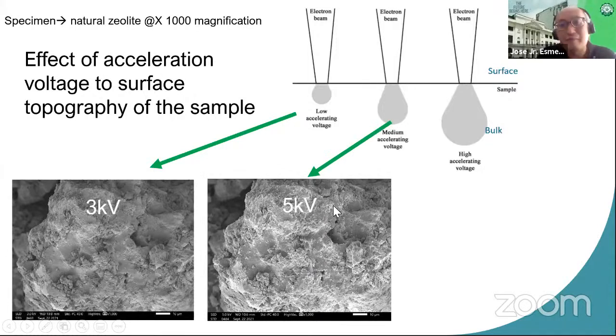We increase the voltage to 5 kilovolts, in the range of 5 to 7 kV, which is medium accelerating voltage. Because the energy of the electrons is higher this time, they penetrate further. So what does that penetration do to the image? You can see a lot of bright spots. Electrons tend to get trapped on the surface, creating some sort of charging, which creates brighter contrast. At the same time, you can see a lot more details beneath. So that's the main difference. You get more details at 5 kV.